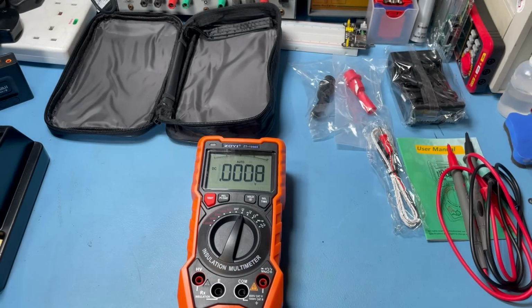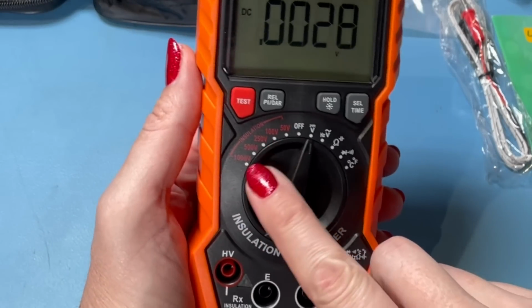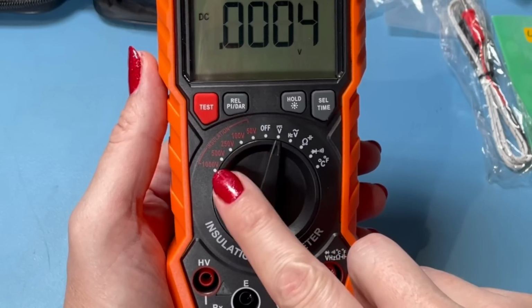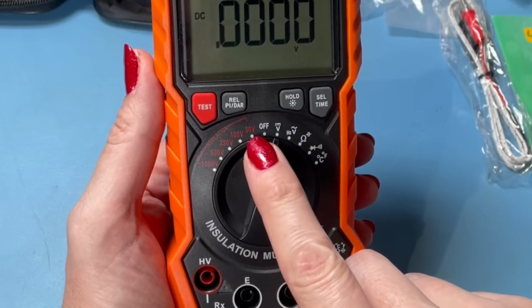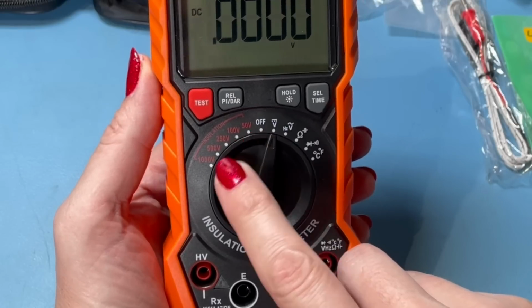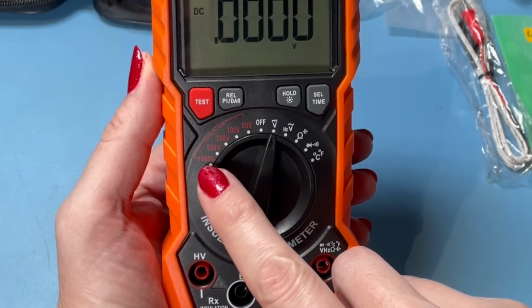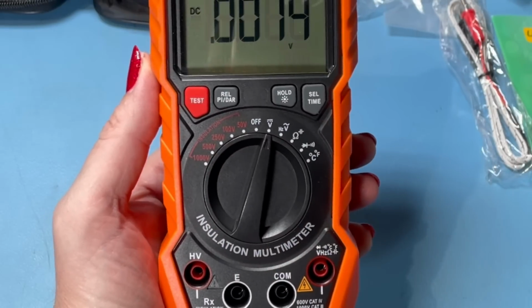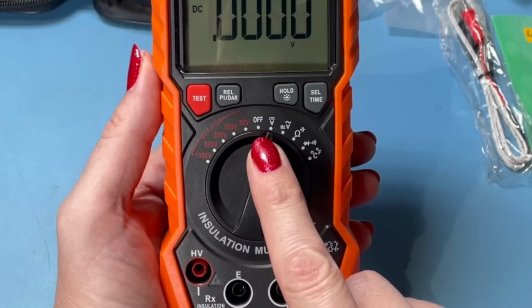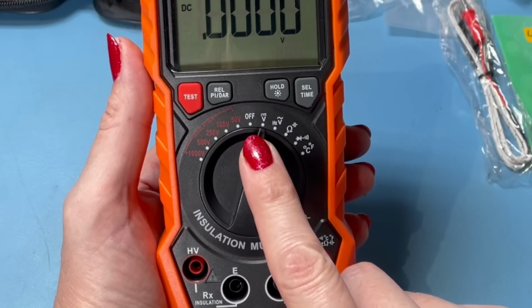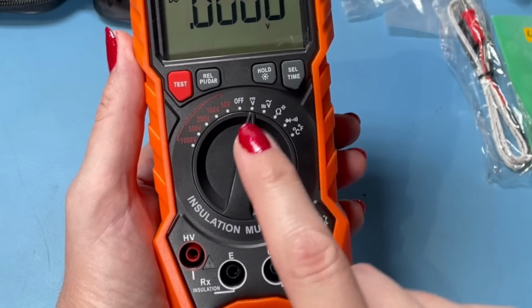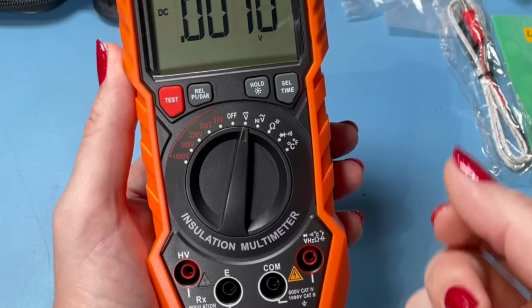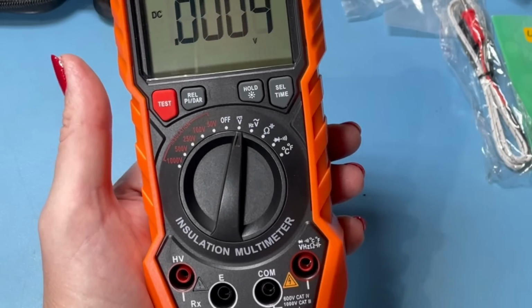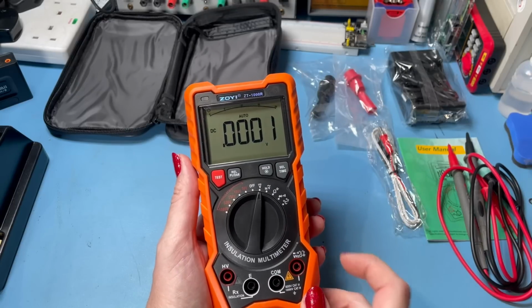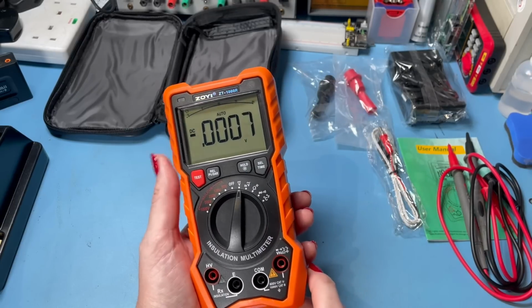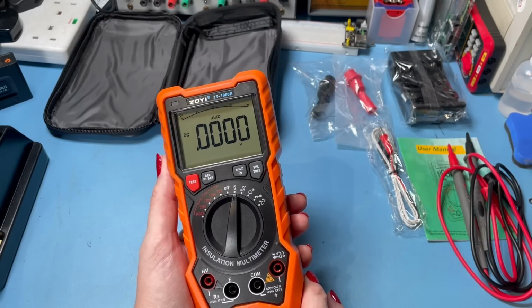There we go. So you can see you've got your Megohm functions here. You've got your insulation tests here, look, and you've got ranges from 50 volts. You've got 50, 100, 250, 500, up to 1000 volts. This does AC and DC voltage up to 1000 volts and all the usual suspects: resistance, capacitance, diode mode, continuity, frequency and temperature. And the temperature range on this goes from -20 degrees C to 1000 degrees C, so it's a pretty good range.